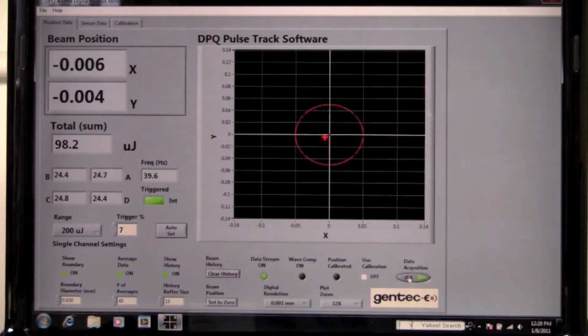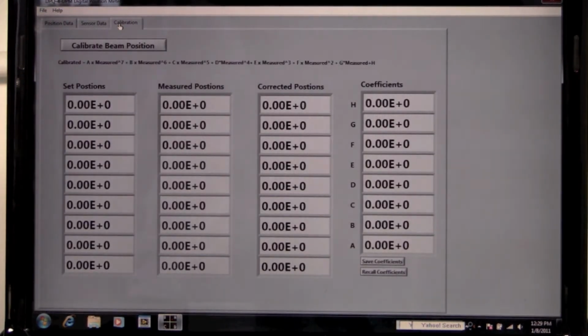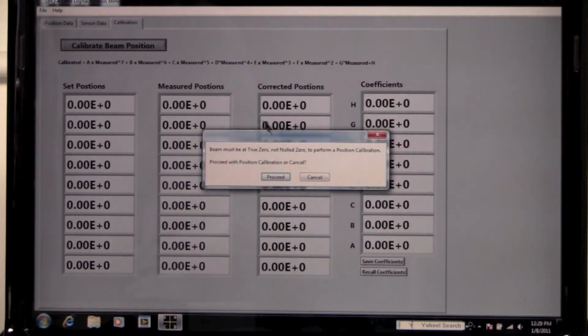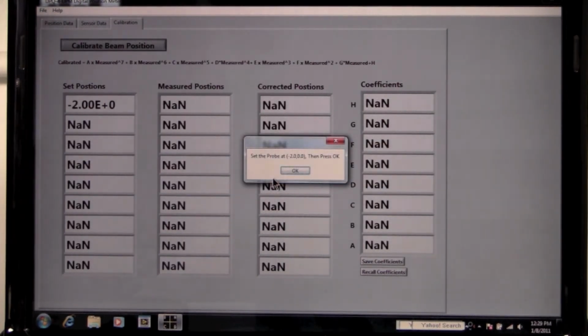Let's talk about position calibration. Quadrant detectors are inherently nonlinear as the beam moves farther from the center. So, we've developed a unique method for calibrating the quadrant detectors for round uniform laser beams. Let's take a look at the calibration screen and I'll walk you through calibration. It requires the quad probe be mounted on a micrometer-driven XY stage and that you find the physical center before starting. Here you see the table with 9 set positions.